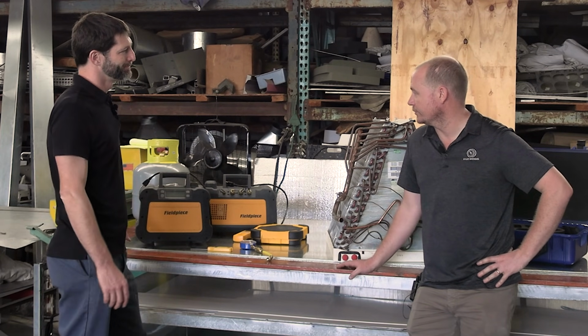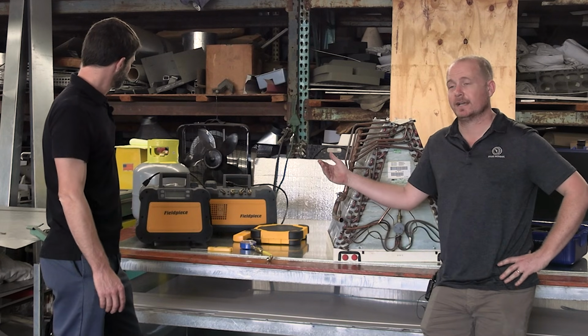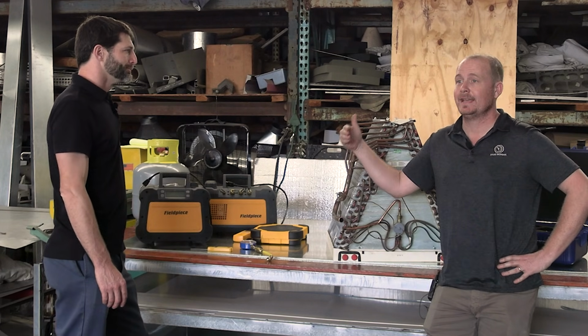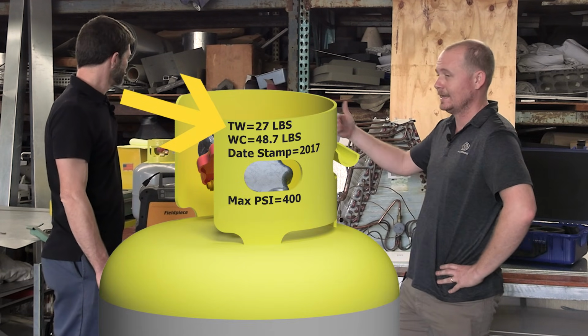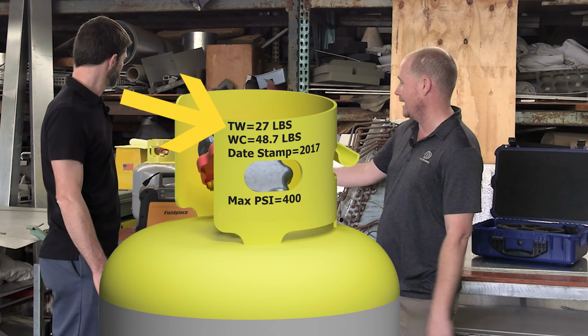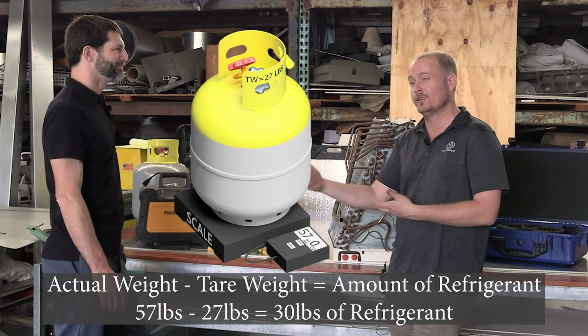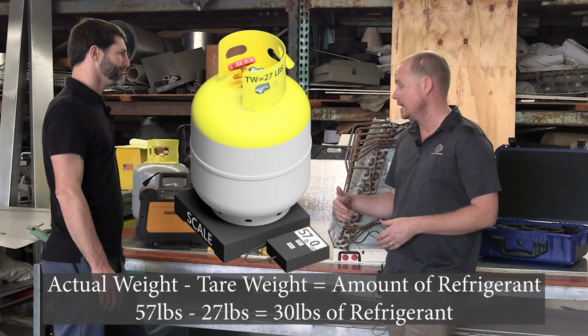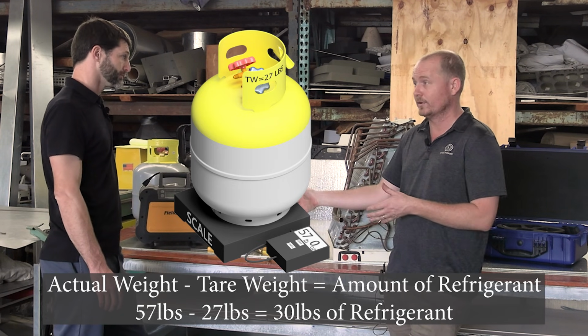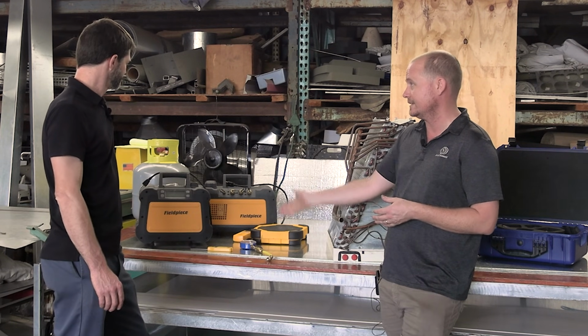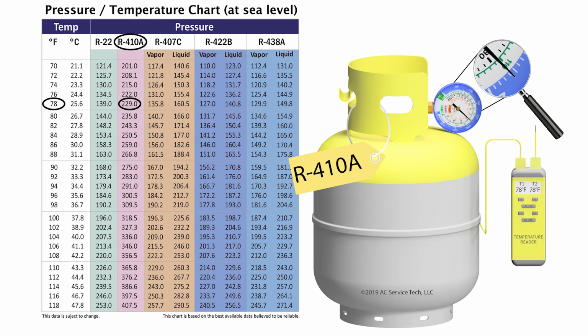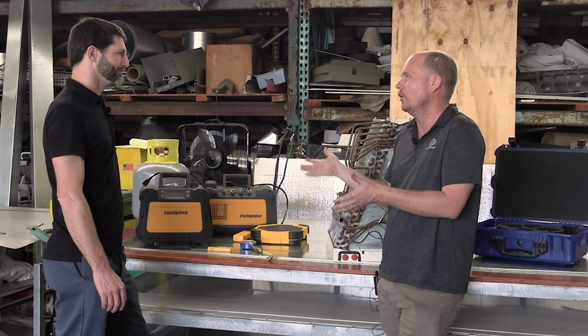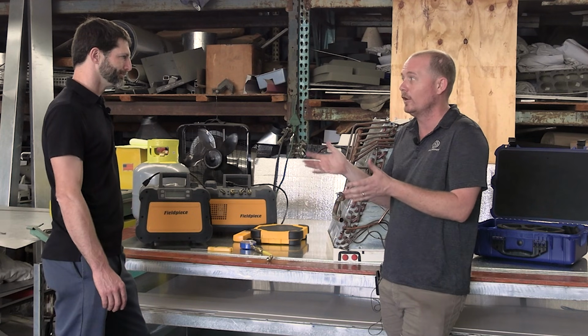Yeah, and that's really simple to do in order to calculate how much is in the tank, because the tank has stamped on it its TW, or tare weight, which is its empty weight. You just compare what you actually measure with a scale to that tare weight to know what's in the tank in the first place. To go back quickly, though, you also want to know what refrigerant's in it, and that's where just connecting a gauge to the tank, comparing it to a PT chart, to a known refrigerant based on, generally speaking, it's going to have on there what the tank has in it, hopefully.